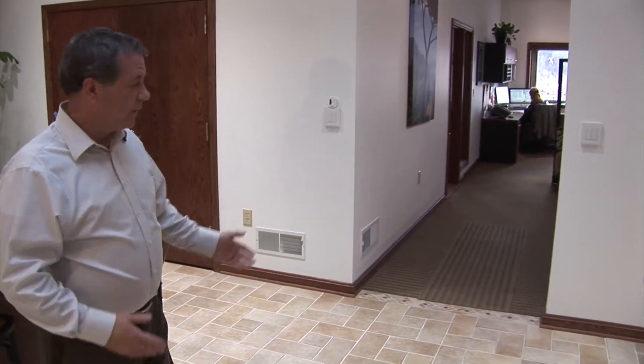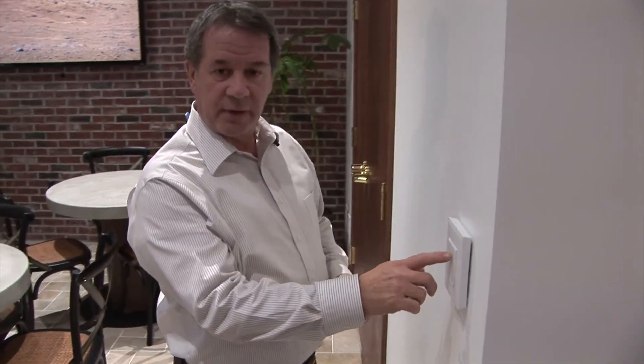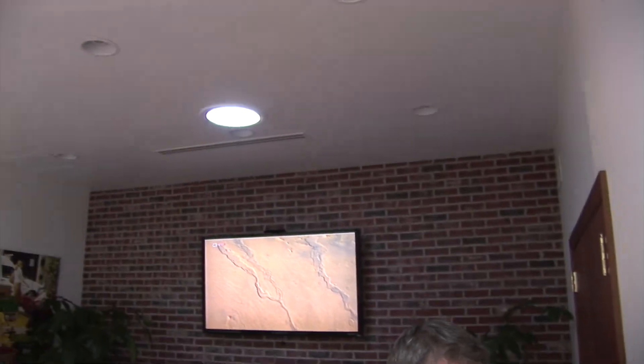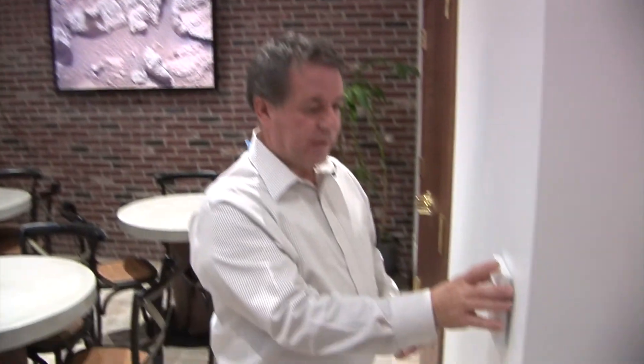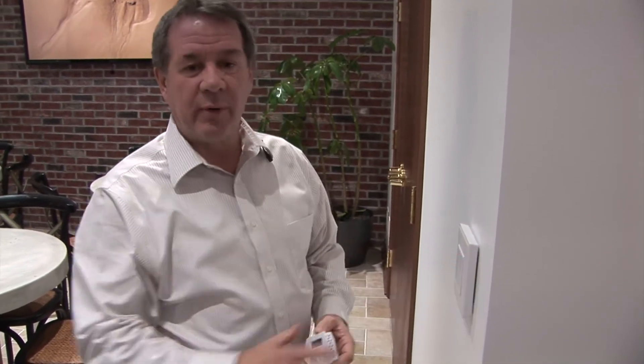The lights are controlled by light level sensors. To turn the lights on and off, we used EnOcean wireless switches — and we wanted those on both sides of the doorway, with two doorways going through the kitchen. Here's our temperature sensor for this VAV zone, and these are the light switches. As you can see, these are just Velcroed to the wall — no wiring. So we were able to put in four-way switches, which would be complicated to wire, but with wireless you can put in as many switches as you want controlling as many lights. No complication, no wire, very inexpensive.